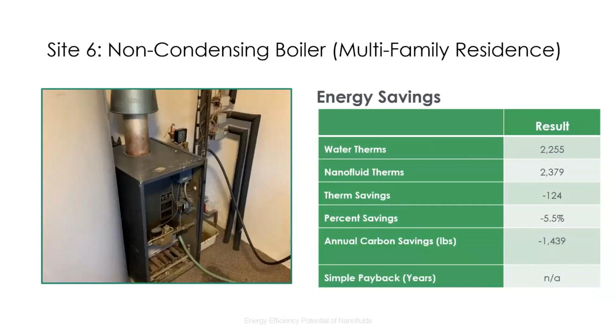Our sixth and final site is a non-condensing boiler in a multifamily residence. It serves hot water baseboard radiation in a fourplex. And the energy savings summary at the right shows negative gas savings. We have a little bit less confidence in these results just due to the higher potential variability in the occupant schedules, with it being a fourplex. Though the occupants didn't indicate as such through a customer survey, their daily schedules may have been impacted by the stay-at-home orders in 2020.